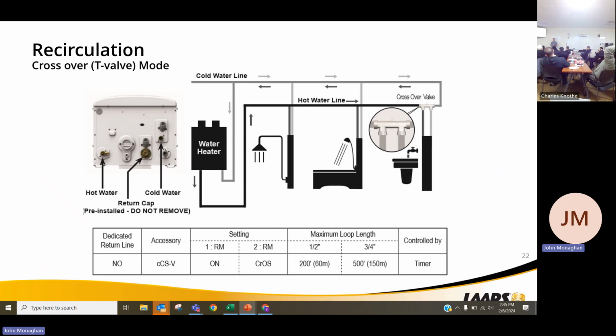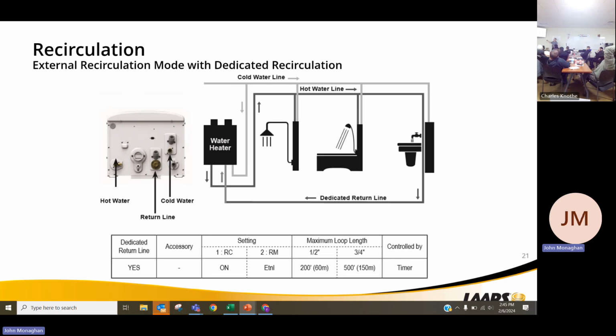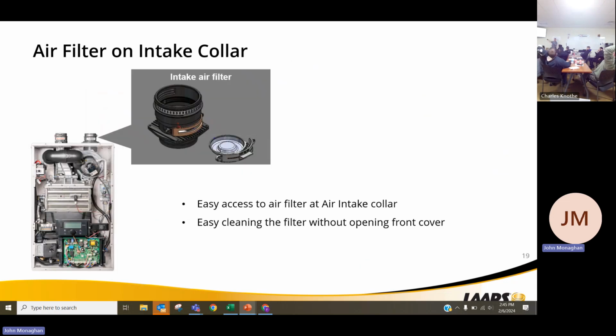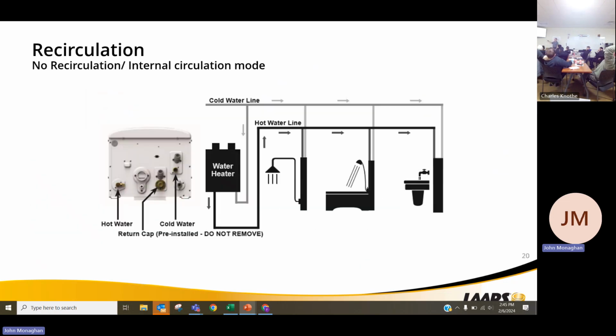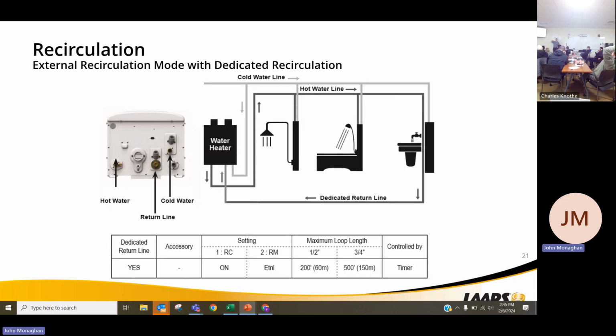The unit will fire. It'll turn the unit on. That's why when we go back to turning off that flow sensor, the flow sensor is usually what engages it to fire. So when we set it for cross, we're going to turn that flow sensor off, so it knows that, hey, I may not have flow, but I need the fire. I need to make hot water.